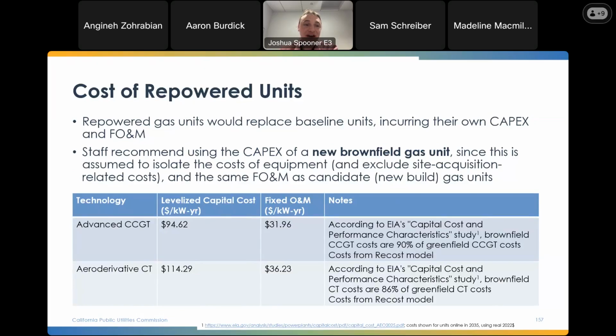When it comes to the cost of repowering units, there is a CapEx or capital cost portion and a fixed O&M portion. For the capital cost portion, we are assuming the cost of a new brownfield gas unit. This is meant to isolate the cost of equipment, essentially of building a new turbine, and excludes site acquisition costs, since this would be a repower of a unit on an existing site. So for combined cycle repowers, this would be about 90% of the greenfield costs, coming in at about $95 per kilowatt year.